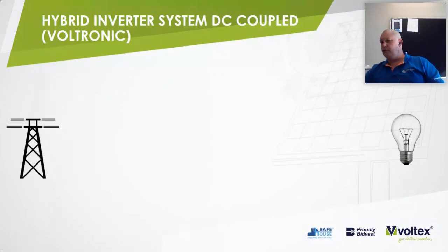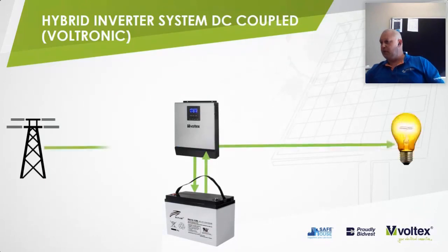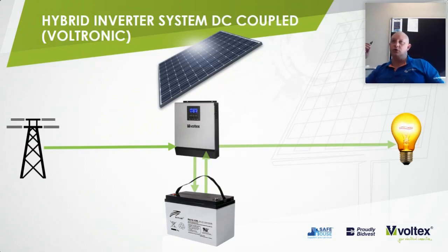So as per norm, you have your utility and your loads. You've got the battery system that we connect and your system that feeds through. By adding solar to the equation, you can supplement power from PV to your loads and generate a saving on your Eskom account. After hours, the system will carry on as normal. You can consume a certain amount from the batteries.